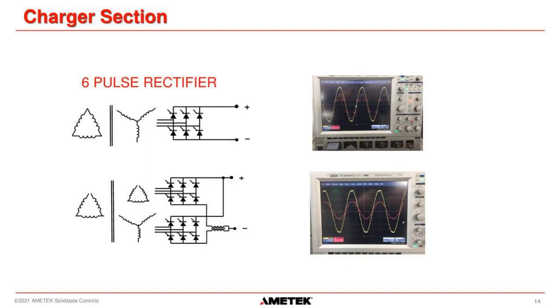So we have two different rectifier designs. The top pictures are for a 6-pulse rectifier. You can see in the waveforms that there's more ripple in this configuration than there would be with a 12-pulse rectifier, which is below.